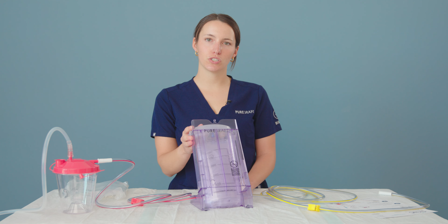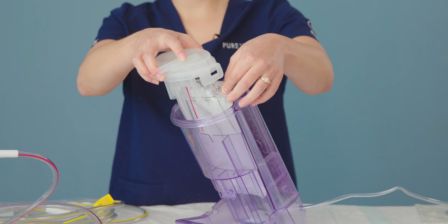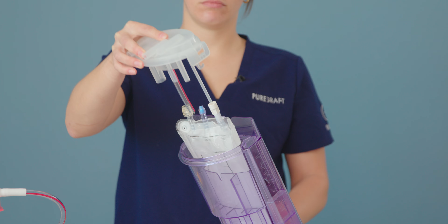Before removing the lid, you will either need to disconnect the tubing from the lid or remove the tubing from the tube holders on the back and sides of the device. Remove the lid from the Puregraft sink device by lifting the tabs on the side of the lid. Keeping the Puregraft filtration bag inside the sink device, carefully remove the bag from the lid. First, unhook the bag, then disconnect the tissue and drain ports. The lid can now be set aside.